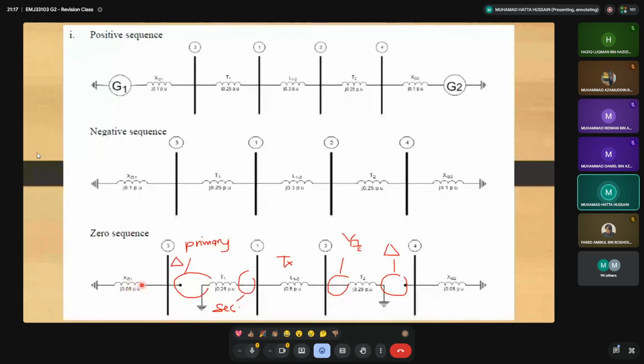For the zero sequence here, the value is referred back to the table, J0.05 per unit. Then going to the transformer, because at the primary side of transformer 1 we have a delta connection, when we draw the delta, this means you open the connection.